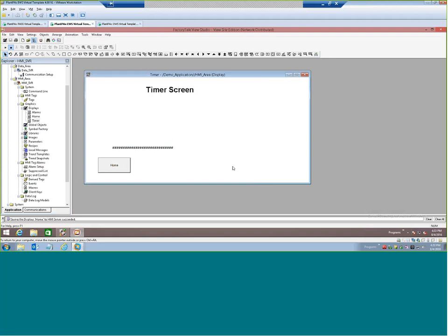Let me see. Is there a way to set up a regular backup using a batch file of the database and application while the server and client are running? What's nice is there is the HMI backup and restore utility, and I think that is open to command line. So I think you could create a batch file that opens up the HMI server backup and restore utility and feed it commands to back up the project.